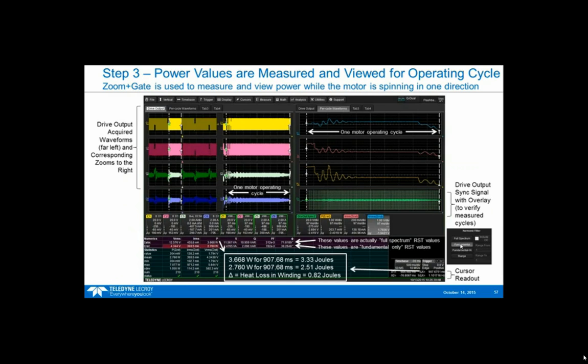As you see in this example, this is obviously a different circuit. When you calculate based on the fundamental versus the full spectrum, the power factor will be quite different, quite a bit higher when you look at just the fundamental. So you have the capability to look at the real sine wave power factor, the displacement power factor, and also to calculate based on the fundamental, the full spectrum, some range, or fundamental plus n.